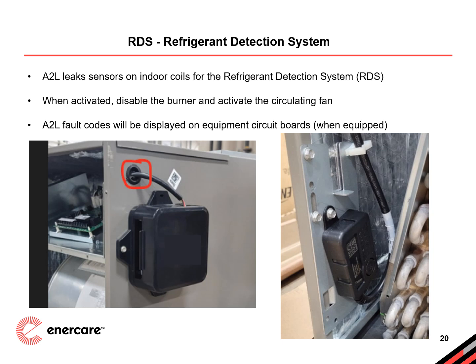Some of the key features of RDS systems across manufacturers are leak detection sensors. Positioned near indoor coils or other high-risk points, these sensors detect the presence of A2L refrigerants. Upon detection of a leak, the system triggers a sequence of safety measures. Activation of the RDS will typically disable the burner or electric heating elements to prevent ignition risks, and initiate the circulation fan to disperse refrigerant and minimize localized concentrations.